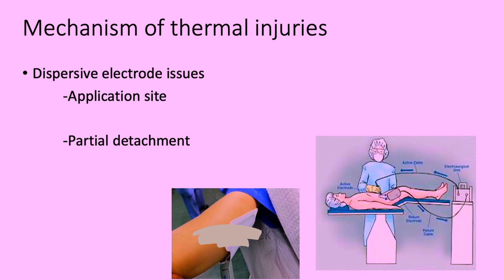Some mechanisms of thermal injuries include issues associated with the dispersive pad — for example, misplacing the pad: if operating in the pelvic region, the pad should be placed under the thigh. You could also have problems with detachment. However, there is a return electrode monitor on the ESU generator — it turns red when the pad has fallen off the patient and green when it is still attached.